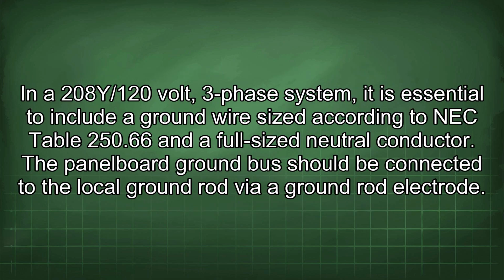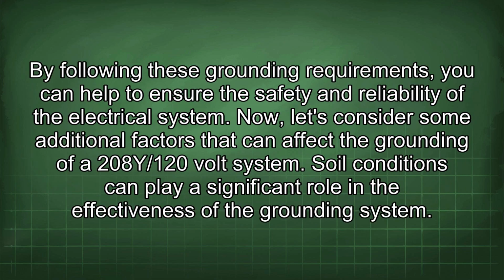In a 208Y/120 volt, three-phase system, it is essential to include a ground wire sized according to NEC Table 250.66 and a full-size neutral conductor. The panelboard ground bus should be connected to the local ground rod via a ground rod electrode. By following these grounding requirements, you can help to ensure the safety and reliability of the electrical system.